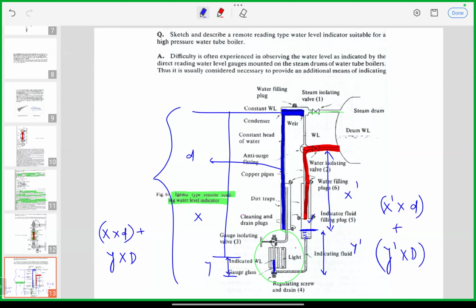That is the working principle of this type of gauge, generally used for remote identification of level. The heavier density fluid will always be proportionally displayed in this U type of column. Wherever density is higher, that side will have more head; the side with lower density will have less head, and due to that density difference you can determine the level at the remote location.